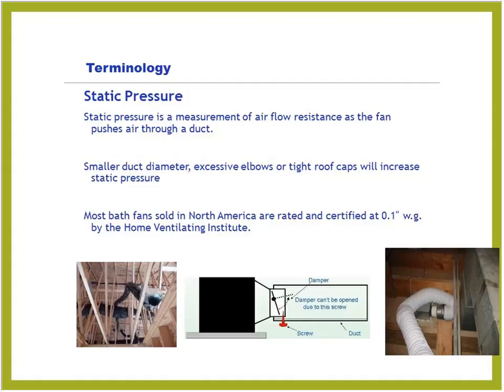And then the picture in the middle, attaching mechanical ventilation requires attaching hard pipe, galvanized pipe, requires some screws to hold that in, and it's not uncommon on occasion that we'll get a call that the fan is too noisy, it's not performing right, and they did all the things right. They used hard pipe, they kept it short, not too many elbows, it went right to the outside, and oftentimes it's either a screw that's pinning the damper shut, or they'll forget to take the tape off of the damper before they do the install. So either one of those can be common install problems.